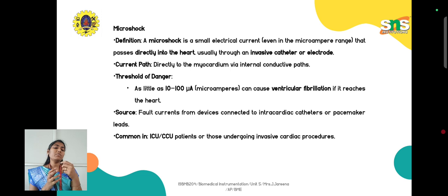So in which case will this type of microshock occur? Whenever we are using any invasive materials, like catheters, invasive electrodes or needle electrodes, there is a high chance for the person to get a microshock, because these accessories make direct contact with the targeted place. That could be the heart or some other organ.